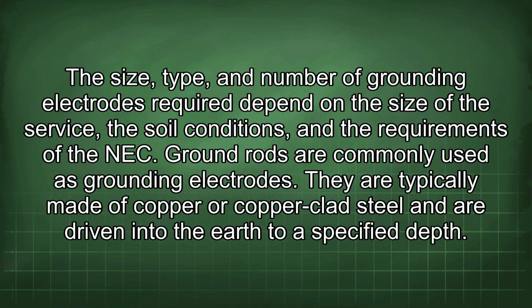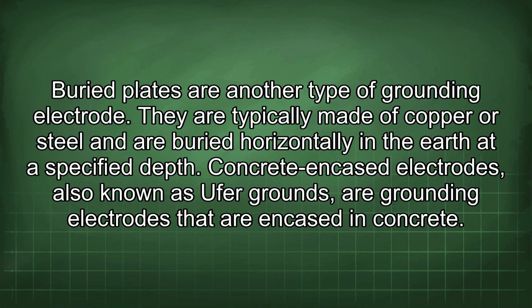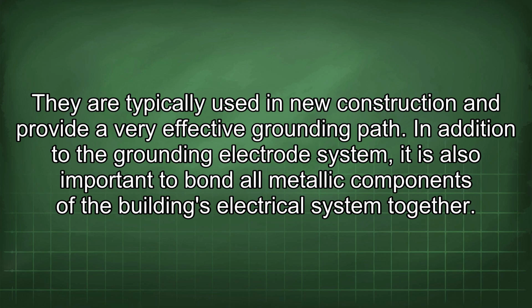Ground rods are commonly used as grounding electrodes. They are typically made of copper or copper-clad steel and are driven into the earth to a specified depth. Buried plates are another type of grounding electrode. They are typically made of copper or steel and are buried horizontally in the earth at a specified depth. Concrete-encased electrodes, also known as UFER grounds, are grounding electrodes that are encased in concrete. They are typically used in new construction and provide a very effective grounding path.